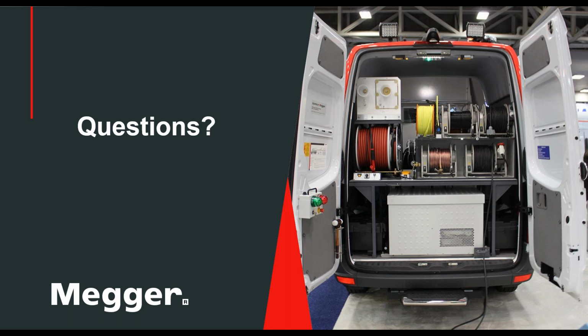In many older circuits in the downtown areas, you have XLP and maybe EPR, and that's not an issue. But if you have paper cable also involved, then paper cable fault locating can be a little different than what Marshall described in his presentation, which was geared around XLP cables.